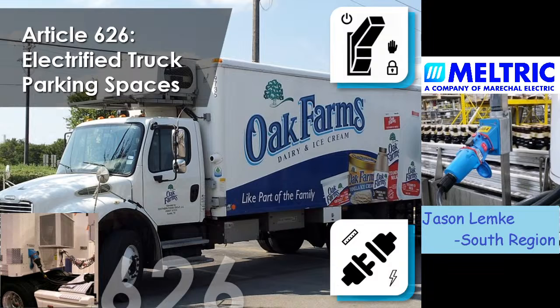So with a Meltric device, we have some additional requirements that we need to meet in order to have our horsepower ratings on our devices, in order to be able to do that closing on a fault. And it's a particular term in the plug and receptacle world called short circuit make and withstand. And what the test is, basically, we fault one end of the plug and we close on that fault. And what we're looking for is what is the amperage that we can have through the plug and receptacle without a catastrophic failure for an amount of time. So in those instances where we have the ratings on the plugs, these short circuit make and withstand ratings, also sometimes referred to as AIC ratings, our devices depend a lot on what is upstream of the Meltric device. What is the overcurrent protective device that's upstream of that?